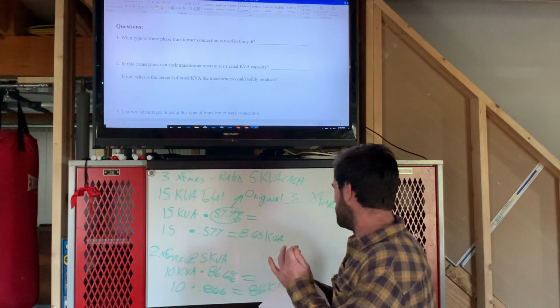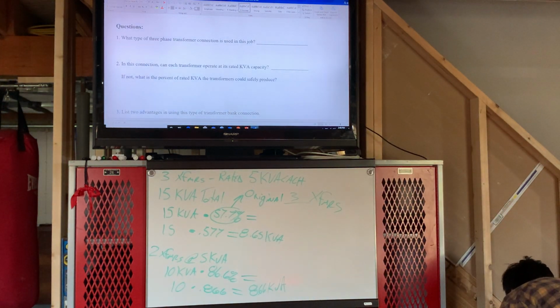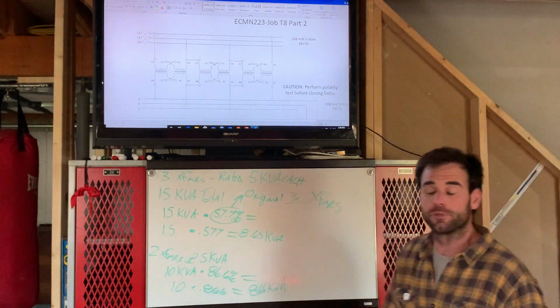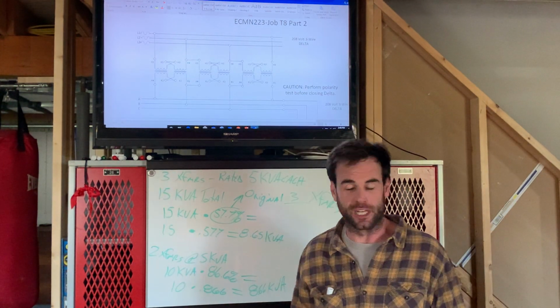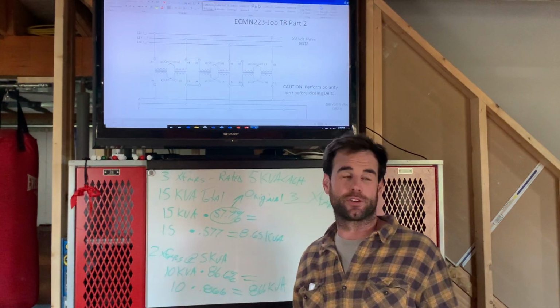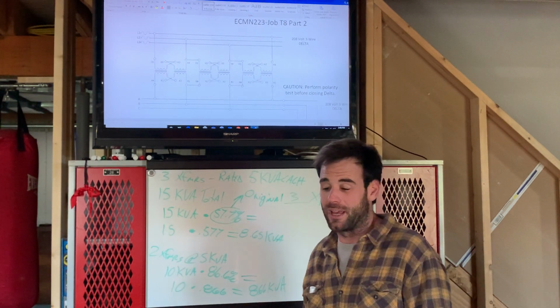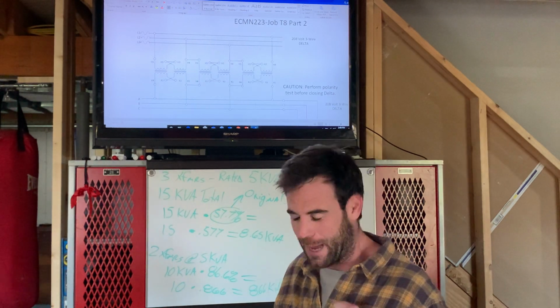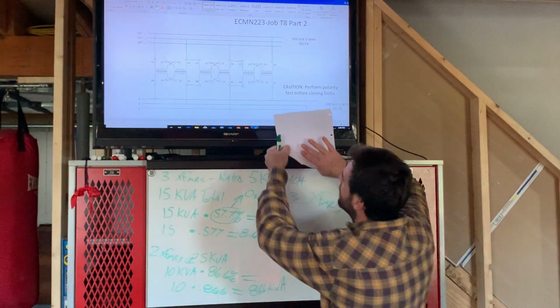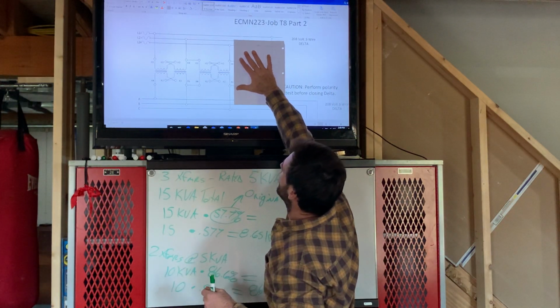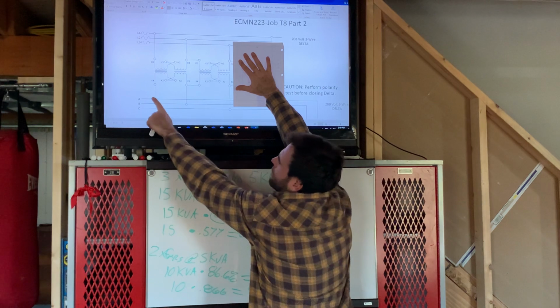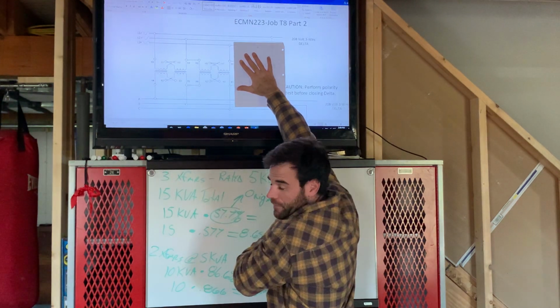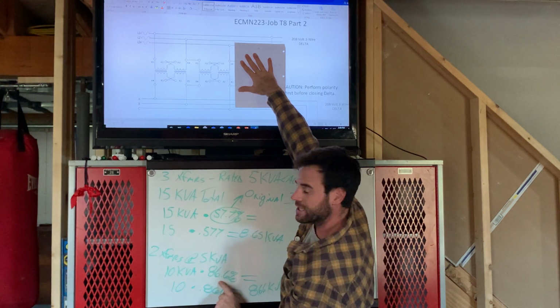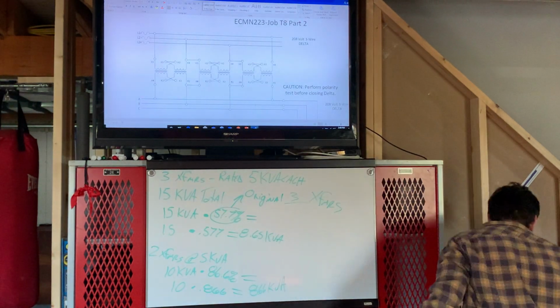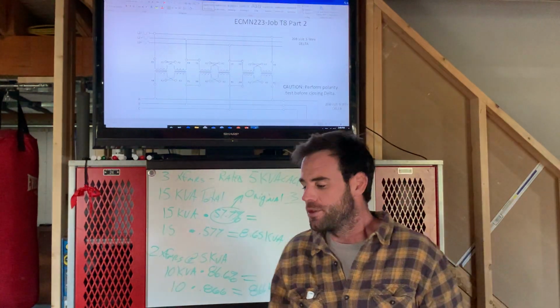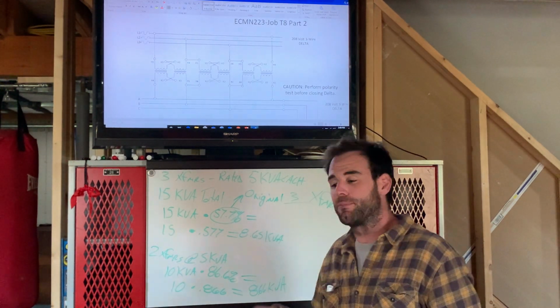Well, if we went through and you had, say a storm went through, the storm we just had came through, knocked out one of your transformers at your business. You don't need every piece of equipment to run on Saturday, but you'd like some equipment to run on Saturday, and the transformer's not coming in until Monday morning. This happened on a Friday afternoon. Well, what you could do is disconnect that 3rd transformer, and you're back to your open delta with 1, 2, 3 phases to provide 3-phase power to your building at a reduced kVA. And the other one is future expansion. You had a small business, you could operate at an open delta, and then when the business gets bigger, put the 3rd transformer in.